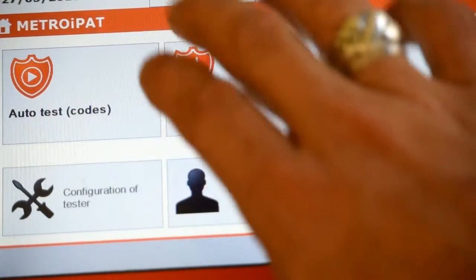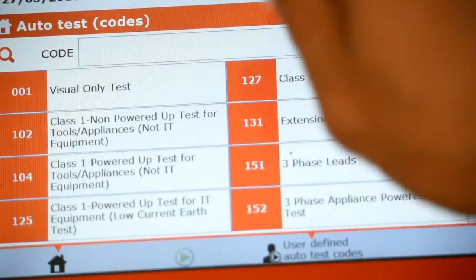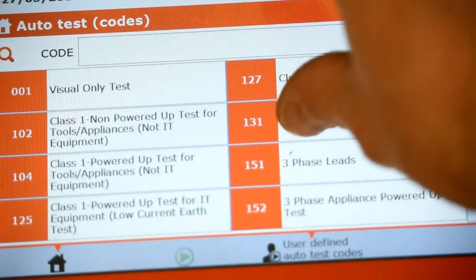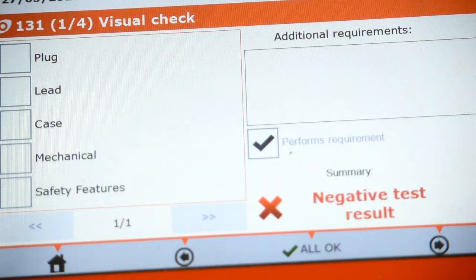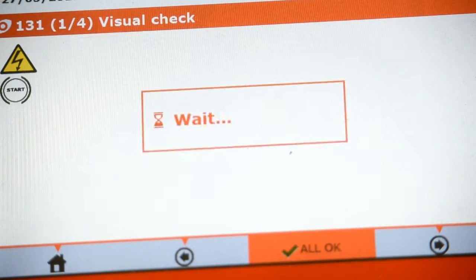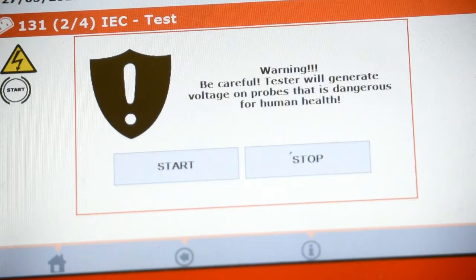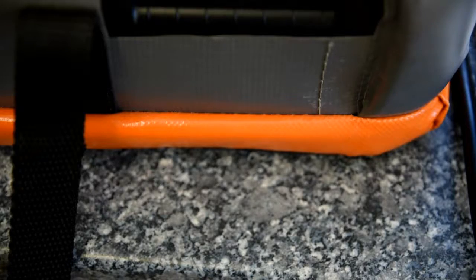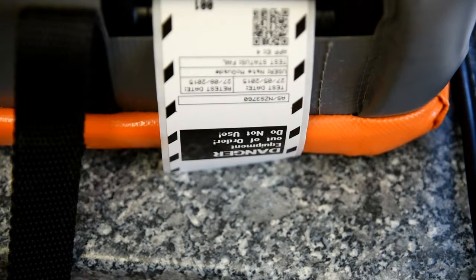When we test for safety in the protective earth, we can do a hard or a soft test. The hard test puts through a really high current, and the soft test puts through a low current. The low current is safe for sensitive gear like computers. But don't worry, the hard test, even though it's a high current, it's not enough to damage your equipment.